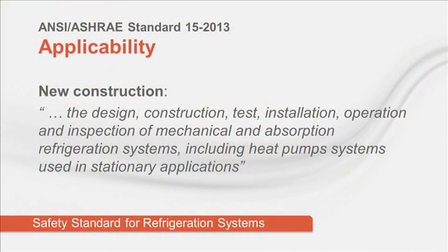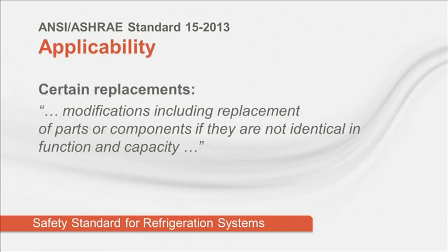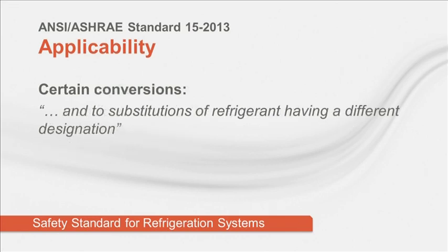The next step is to determine in which situations Standard 15 applies. Basically, there are three triggers. The first is new construction. Whenever a refrigeration system is installed in a new building, the design must comply with the current code. Once the building is finished and approved, no further upgrades are required to keep up with revisions in the code unless one of the following changes is made. A modification to an existing system that changes the size or function must comply with the current version of the code. Basically, replacing a failed part with a similar one doesn't require a code review. But adding an additional indoor unit to an existing VRF installation or replacing an existing unit with one that is larger or smaller will trigger a code review. And finally, compliance with the current code is required when a refrigeration system is converted to a different refrigerant.